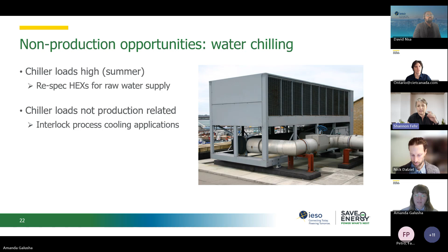Also, the forestry industry, we work in an environment that's highly fouling. So air exchangers or air dumps on our chilling equipment or cooling equipment can be very challenging to operate, giving low efficiency for the energy you're putting in. You don't get very much cold water out. One way to avoid that is simply by speccing all of your heat exchangers in your process for your raw water temperature, and then you can focus your chilling on space cooling. That's an example of a place where we can save quite a bit of energy, on the order of megawatts, depending on your facility.